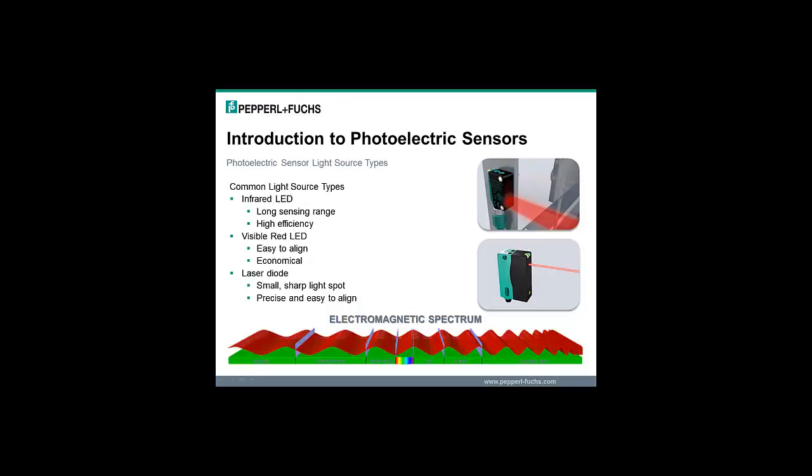The LEDs most commonly used in the construction of a photoelectric sensor operate in either the red portion or infrared portion of the electromagnetic spectrum. Infrared LEDs are the most efficient transmitters and can be driven by large current pulses. They have a high power output and are used to obtain longer sensing ranges compared to visible red LEDs. Visible red LEDs are the most common and most economical LEDs in use, due largely to being able to see the light spot with the naked eye, allowing the user to easily align the light beam to the object to be detected.